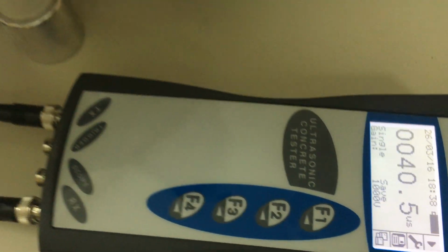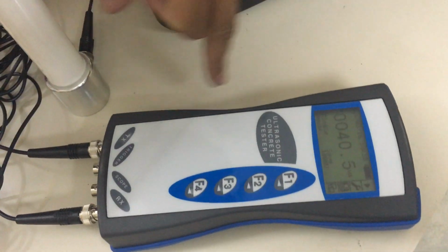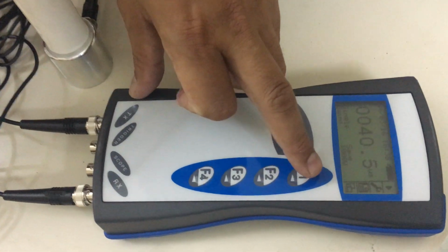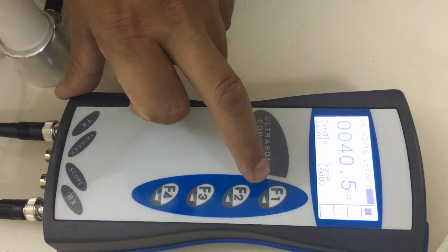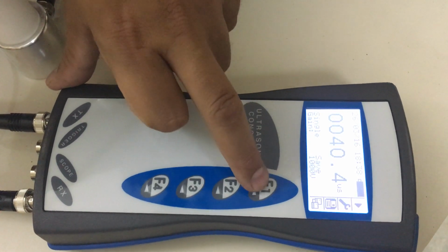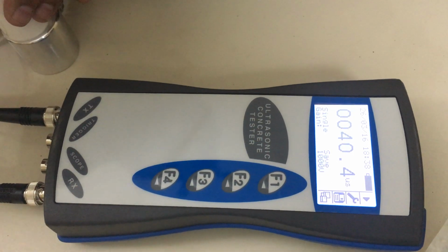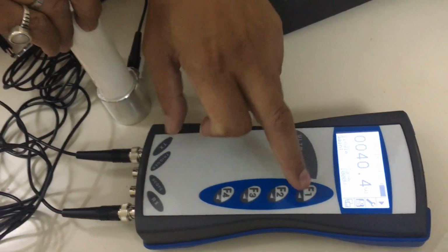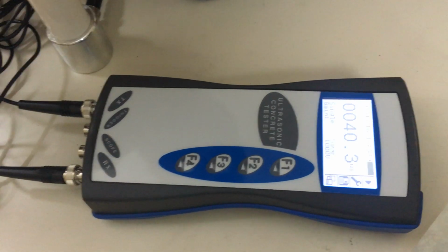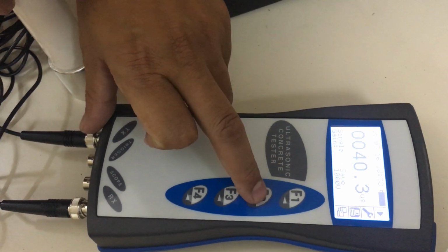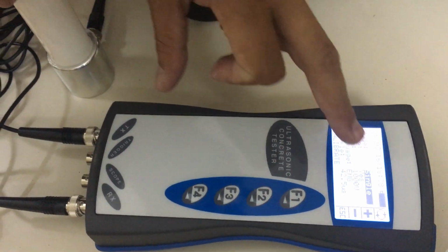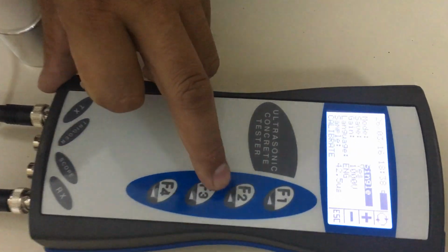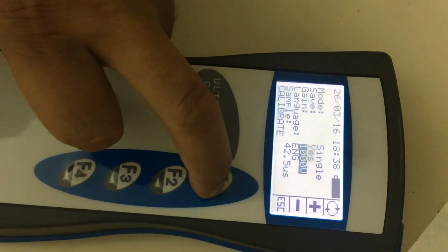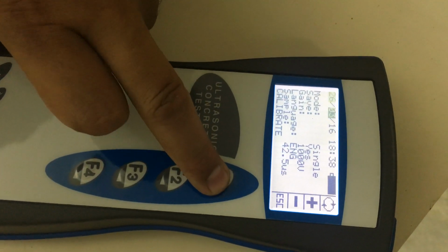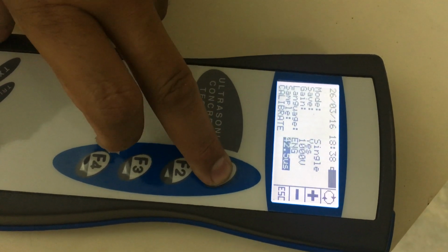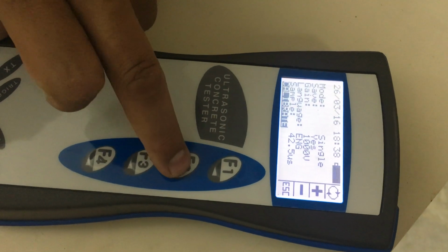So this leads me to calibrate my ultrasonic pulse velocity. So I will now calibrate it. You can see 40.4 or something. I can still do it once again, just verify it. It's still coming 40.3 and 44. So what I do, I go to the setting parameters, go to calibrate by using the scroll key. Oh, it is gone. I have to scroll back again and then select by the plus or minus key.